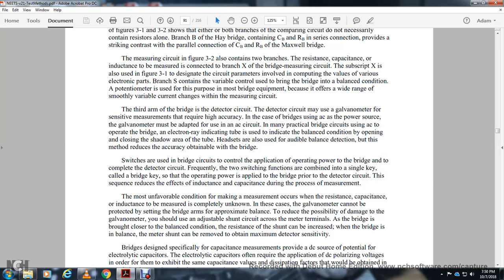The electron ray tube indicates balance by opening and closing the shadow on the tube face. Audible balance detectors reduce the accuracy obtainable with the bridge. Bridge switches control the amplification and operating power. Two switching functions are often combined in a single key called the bridge key, which serves both the power supply and the detector circuit.